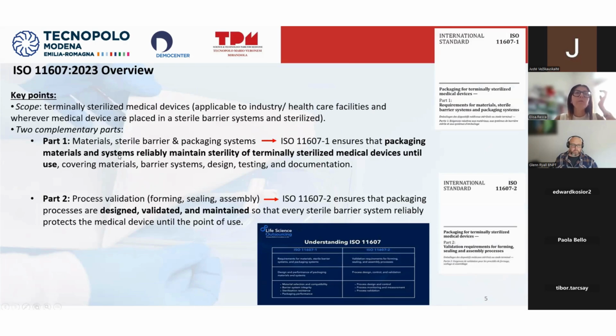So just a brief overview of the ISO. The ISO is the global reference standard for the packaging of terminally sterilized medical devices, and it ensures that the packaging system maintains sterility up to the point of use and is designed, validated, and controlled appropriately. It is divided into 2 parts, part 1 and part 2. The focus of part 1 is the design, material, and performance requirements, and the focus of part 2 is the validation, so forming, sealing, assembling, and ensuring that packaging processes are designed, validated, and maintained so that every sterile barrier system reliably protects the medical device until the point of use.